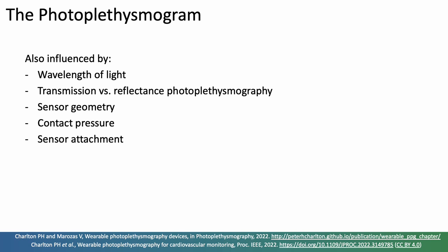The signal is also influenced by the wavelength of light which is used to obtain the signal, the choice of transmission versus reflectance photoplethysmography, the sensor geometry, the contact pressure, and the sensor attachment.